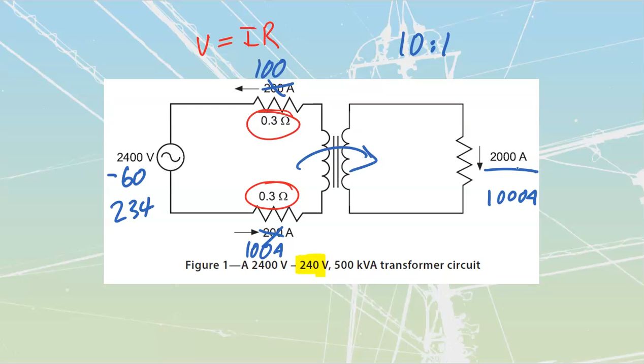they're going to be heavily loaded in the summer as they're stripping out that 30-degree heat from the air and releasing that to the atmosphere. It's a lot of work on those compressors. It's a lot of amps that are going to be taken out of it. But in the winter, all of a sudden, their voltage is going to change. So in some cases, part of your yearly electrical service in some of these plants is going to be changing your transformer taps leading into hot weather and then coming out of it again in October, November, something like that. Otherwise, you end up with too high of a voltage off of there.